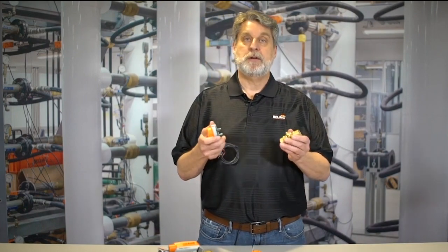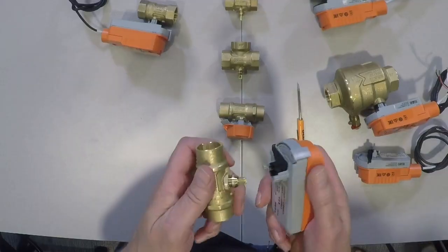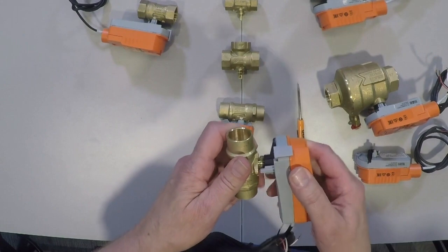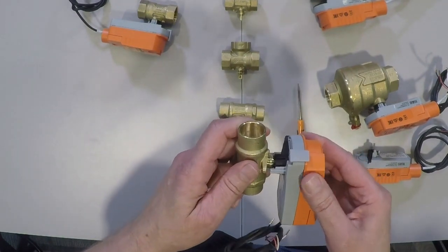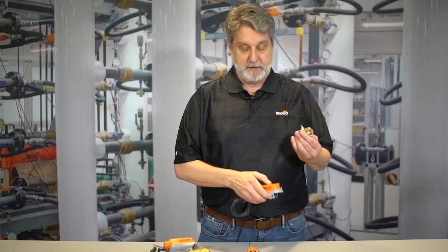So, you come back a couple of weeks later. You're ready to commission the system and test it. You go to put your actuator back on and it no longer matches up. There's two ways that you can take care of this.